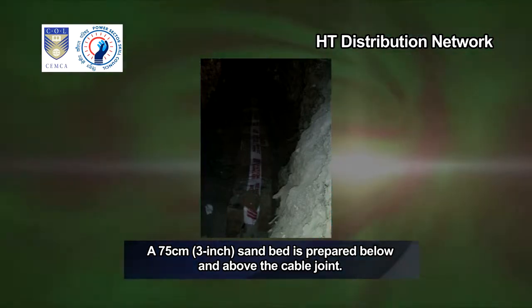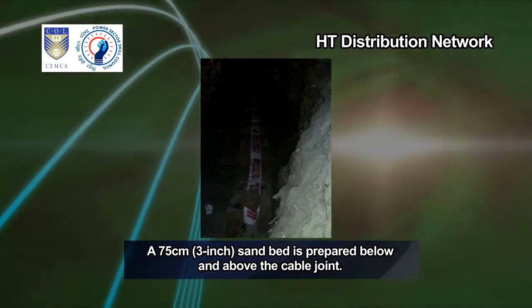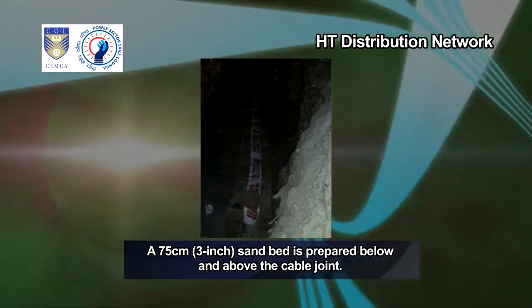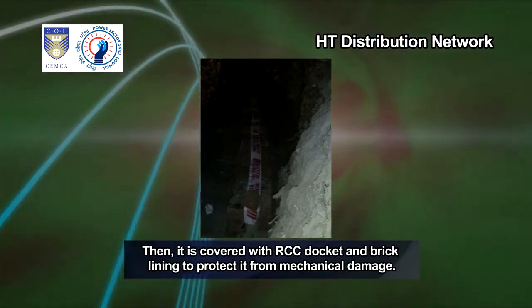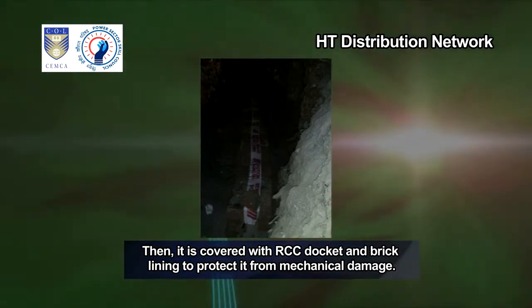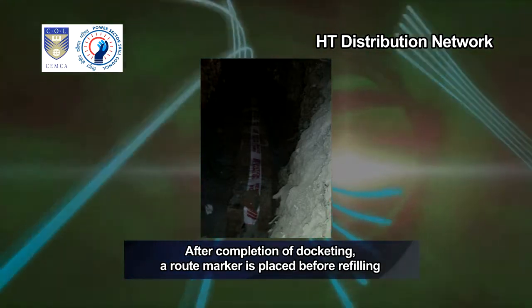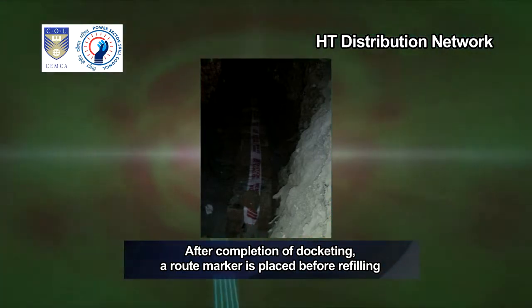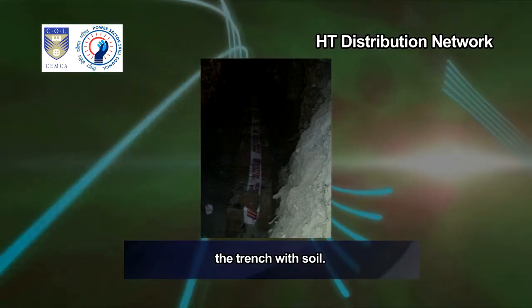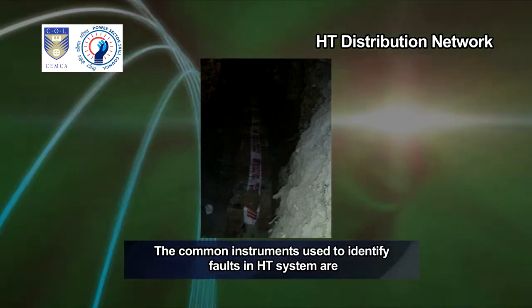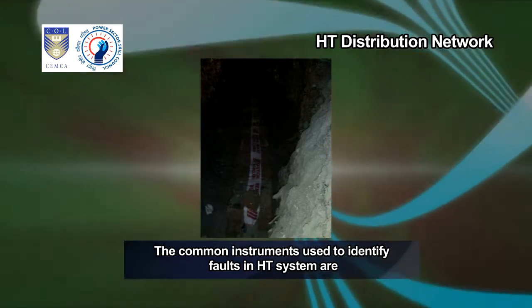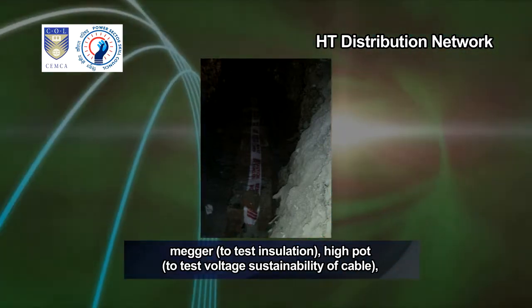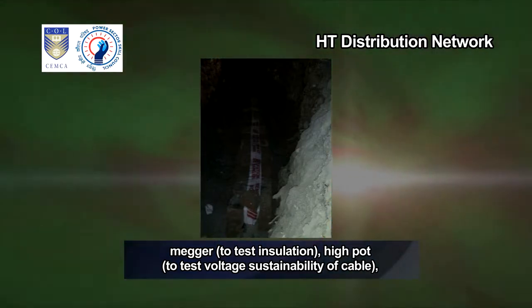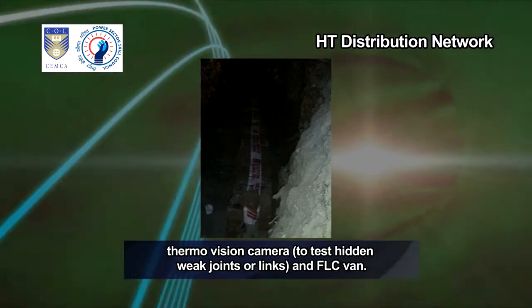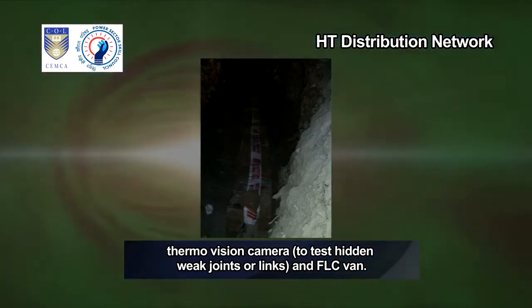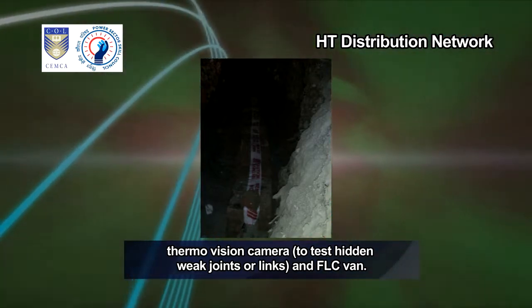A 75 cm, 3-inch sand bed is prepared below and above the cable joint. Then it is covered with RCC docket and brick lining to protect it from mechanical damage. After completion of docketing, a route marker is placed before refilling the trench with soil. The common instruments used to identify faults in the HT system are Megger to test insulation, Hypot to test voltage sustainability of cable, Thermovision camera to test hidden weak joints or links, and the FLC van.